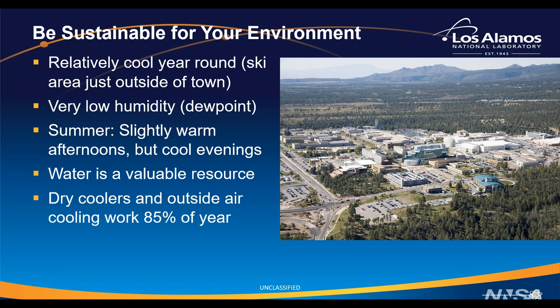It's also very low humidity here. So while evaporative cooling towers work very well, water is also a valuable resource here in the Southwest, where we're located in New Mexico. So we try to be sensitive to the community and conserve those water resources, even though the lab itself does have ample water rights. It turns out that we can use the dry coolers and outside air for 85% of the hours in the year without needing to use water at all.